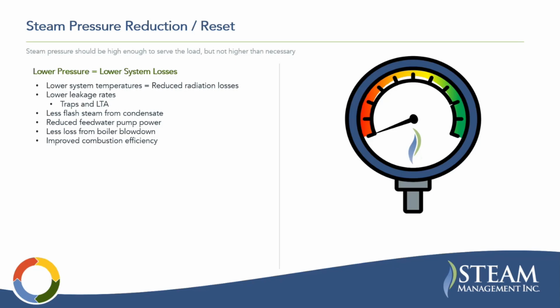And then you're going to improve your combustion efficiency because you're going to increase the differential between your boiler water, which is now at a lower temperature, and your products of combustion.